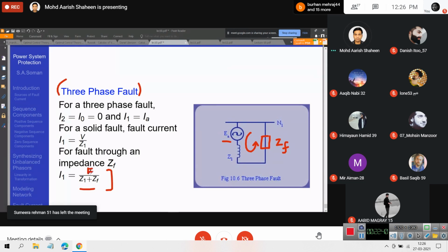ठीक है. Because I have started with three-phase faults, the currents will be equal in magnitude in all phases, and they will obviously be positive sequence, because typically the system itself is positive sequence. We don't have negative sequence generators in a system. All the system generators that we connect are inherently positive sequence. This negative sequence, etc., only arises in the case of an unbalanced fault.